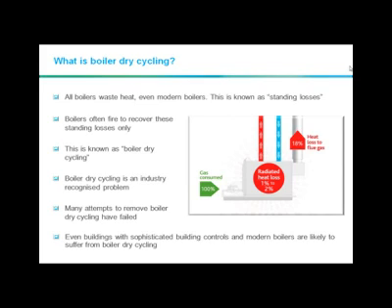It's been there since boilers were designed and manufactured. Many attempts in the past have actually failed. Simple time delays or increasing differential temperatures on thermostats do not work. Even buildings with sophisticated BMS controls very often miss this opportunity for savings.